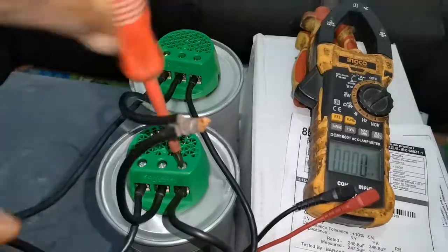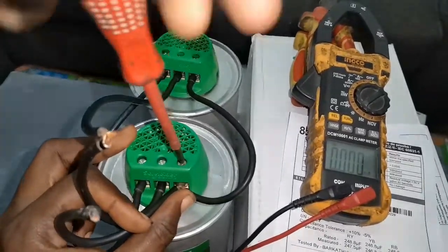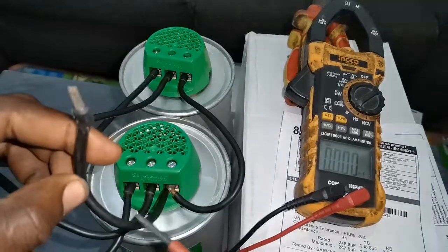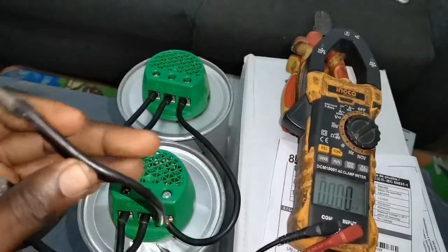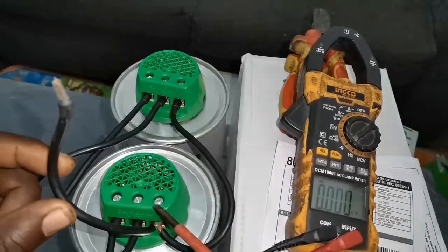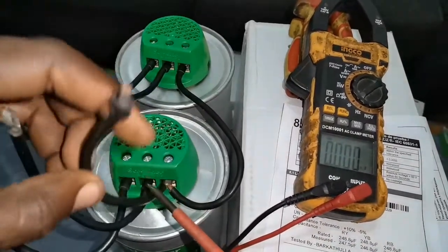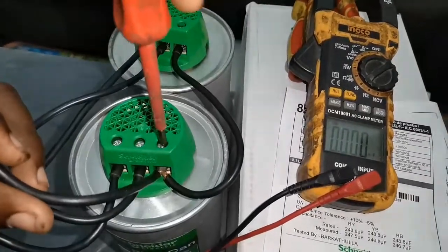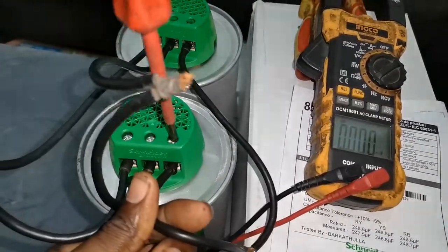Never connect it in this incorrect form — some people loop it like this, going from here to here and just sending this outlet to the contact, which is not accurate and not how it is supposed to be done. By doing it that way, the current flowing here will add up — assuming you have 30 amps flowing here it adds up, which will make this cable carry 60 amps of load, and that is not healthy. The best way is to connect it professionally and accurately.